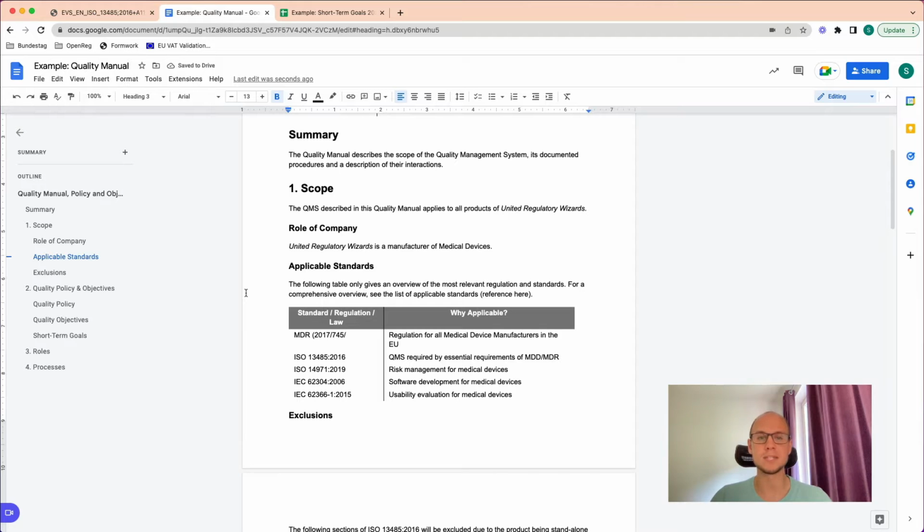The remaining norms cited here are the core standards that apply for software medical devices. There's a whole number of other applicable norms though, such as the ISO 15223 for medical device labeling, or the ISO 27000 series, in case you need to comply with those. That list may grow long over time, so what I've seen often is that companies only really put down a core selection here, and then reference a more elaborate list in a separate document.